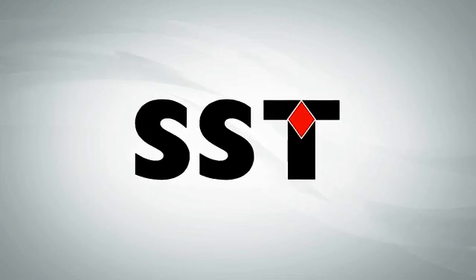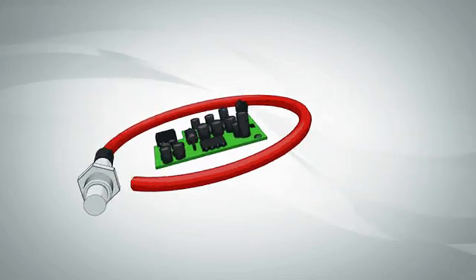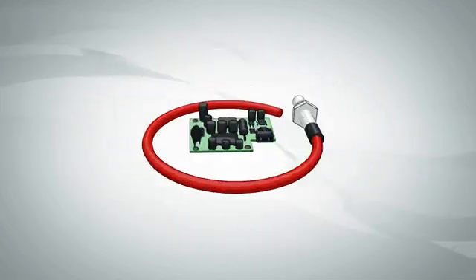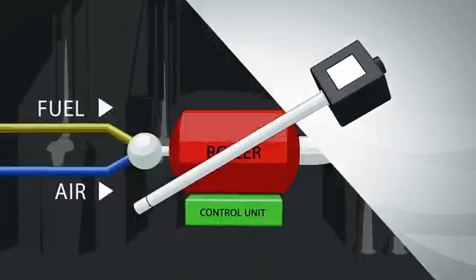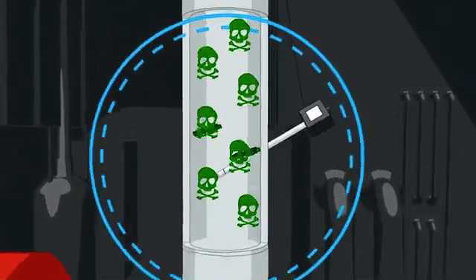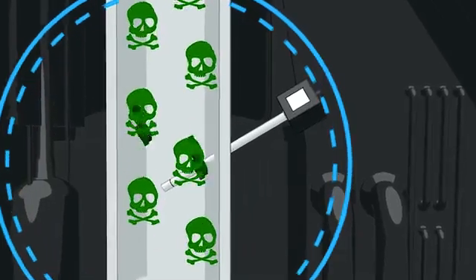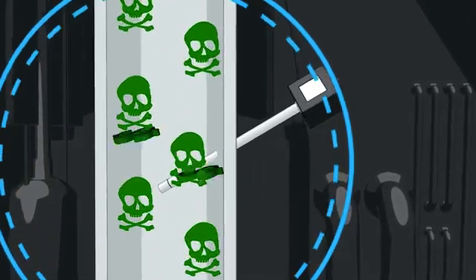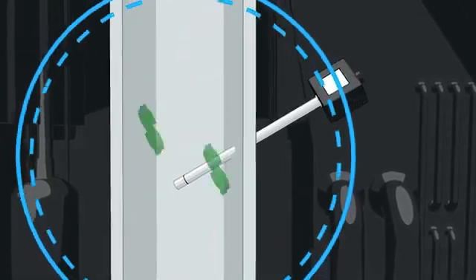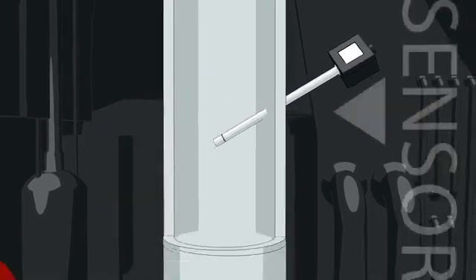SST's zirconia oxygen sensors have been used to provide a clean burn and reduce harmful emissions in combustion processes for over 25 years. The oxygen sensor is inserted into the boiler flue to monitor the oxygen level, enabling complete control over the boiler's air-to-fuel ratio.